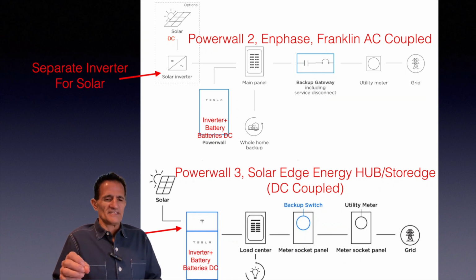Now, the advantage of this is when you're doing a new system, because you don't have to have a separate inverter, it's lower cost. And also it's higher efficiency because you do fewer conversions from DC to AC and vice versa. So the Powerwall 3 has an advantage for efficiency and cost on new systems.